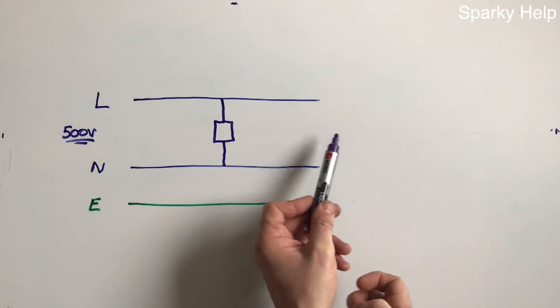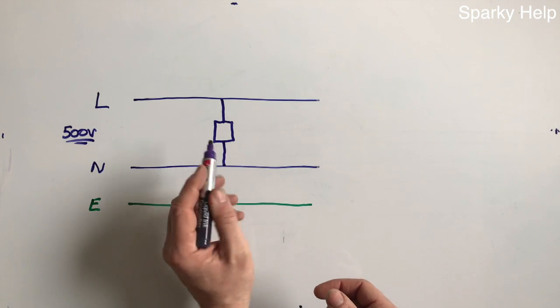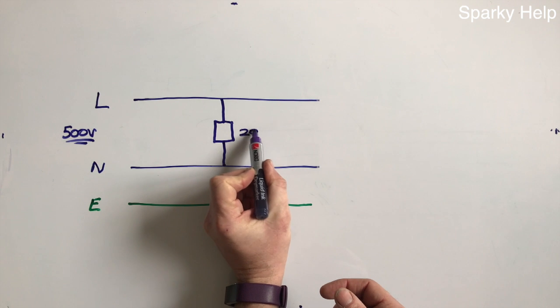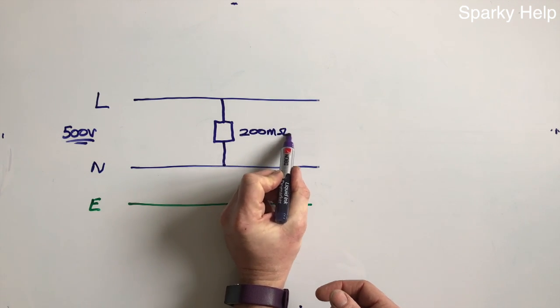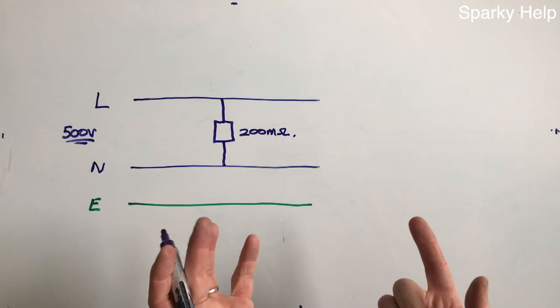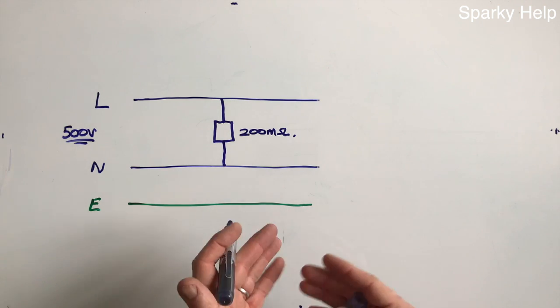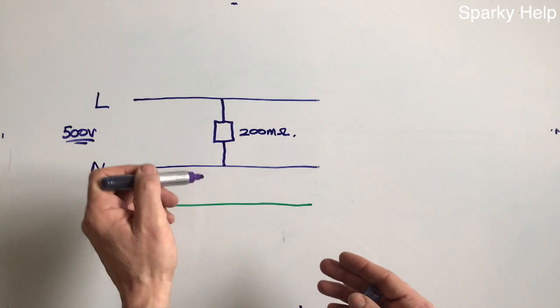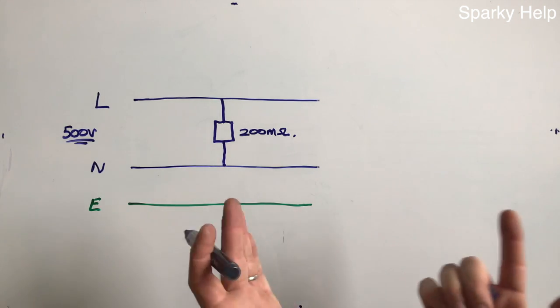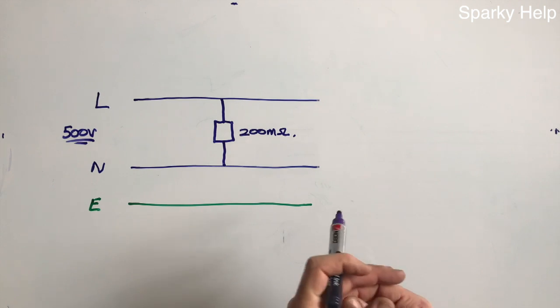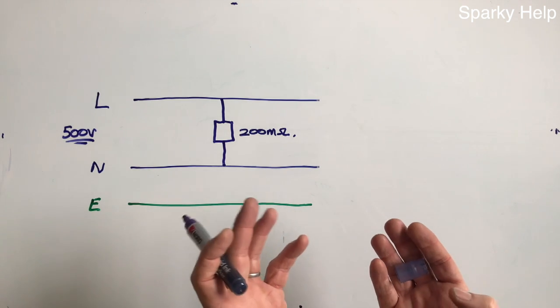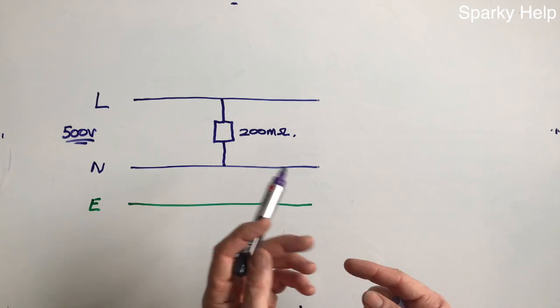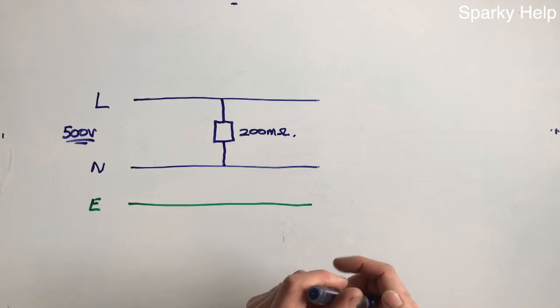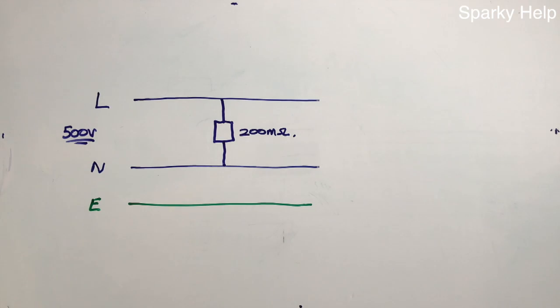So there's a lump of cable that you put in for a specific circuit, and let's say that comes out at 200 mega ohms. So that's basically what it would mean, that you have 200 million ohms of resistance between the two. In other words, they're not touching, it's just insulation. Whereas if you get a dead short, as demonstrated, then a dead short comes up as 0 ohms in this particular case. Now, a question that's often posed is, what happens if you double the length of this?